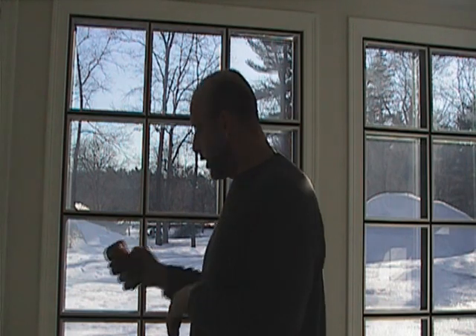They start at 60 degrees — the water in these windows. You can see in the other videos we're looking through four panes of glass, four inches of water — these windows right here behind me. And with a good sunny day, we're looking at about 92.3 degrees as the water temperature in that window right now. So these have come up over 30 degrees over the course of the day, stored in the windows. That doesn't even show you how much energy has actually been contributed into this building. Even though it's only 31 degrees outside, this building has continued to warm a couple of degrees. It will continue to do that well into the night — not only maintaining the temperature in the house, but also raising it. This water will continue to raise the house temperature probably until at least 11 o'clock tonight. We're experiencing 52.7 degrees now, started at 49.7 this morning — up about 3 degrees over the course of the day. That will continue to rise and we'll probably get up in the 55-56 degree range by 9 or 10 o'clock tonight.